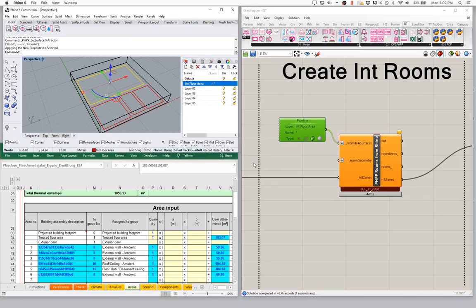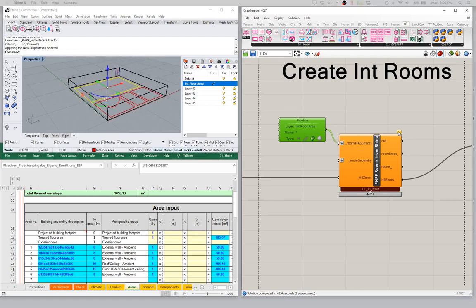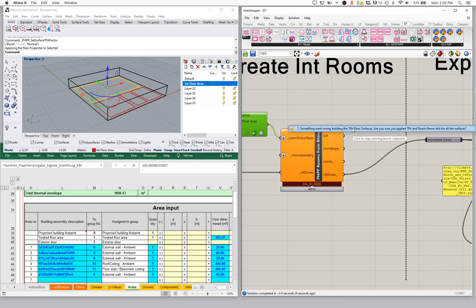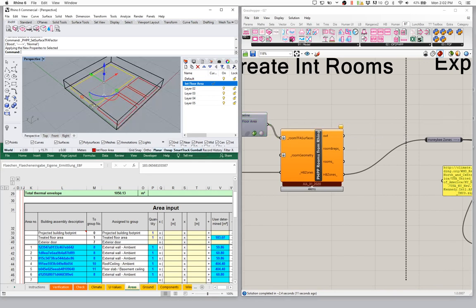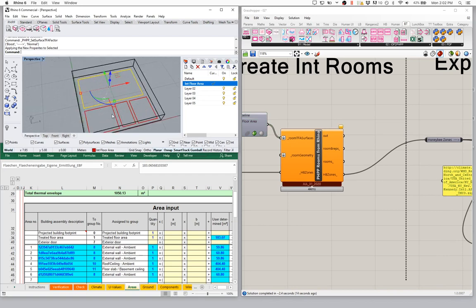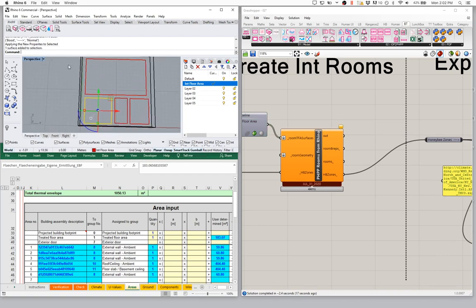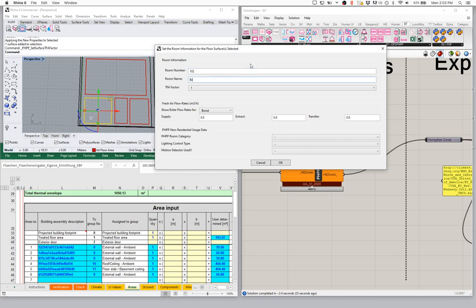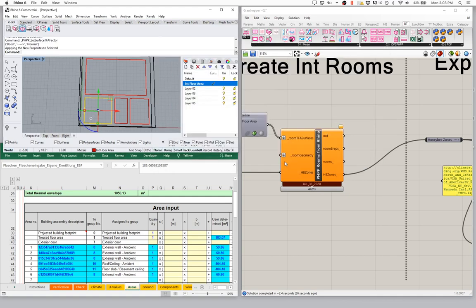Now what's happening at this point? We've passed in the information that we need. I'm still getting my error here — that's because we still have a couple of rooms that we haven't named yet. Let's fill in the rest of these. I'll go to set room data again. This one will be room 102 — let's say it's one of the bedrooms. At normal fan speed a bedroom might have 20 CFM, so maybe 34 cubic meters per hour. OK — and now that one's working as well.